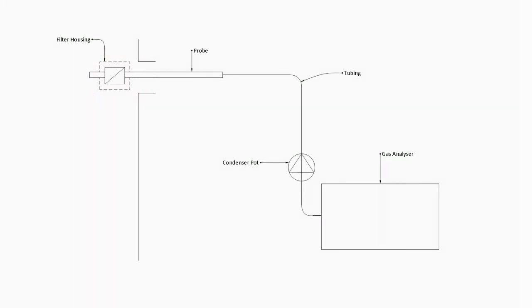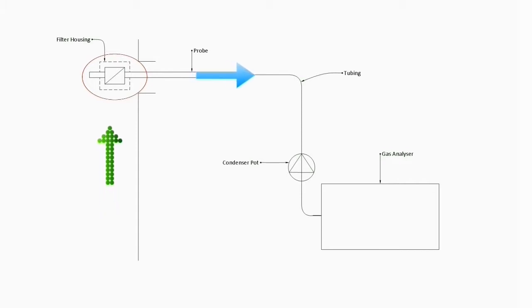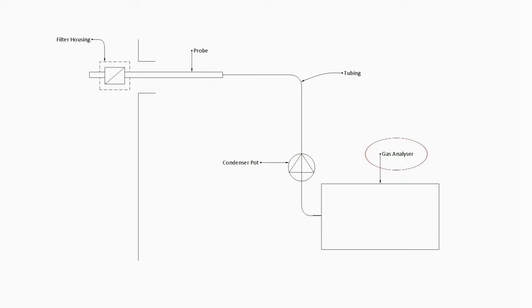A heating system is used to heat the probe and filter holder to prevent condensation before the filter. The filter traps the particulates that may be in the gas stream so that they do not reach the gas analyzer. This is to protect the analyzer from damage.